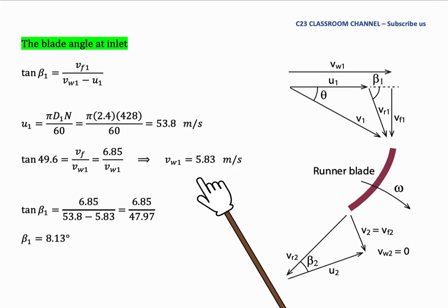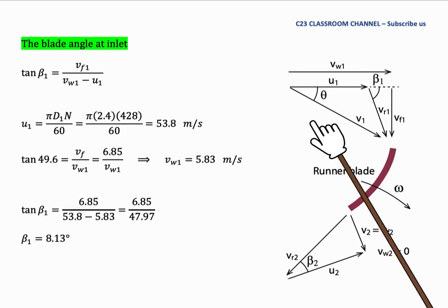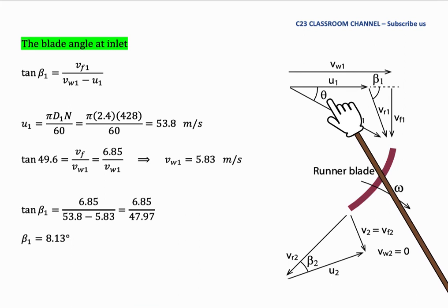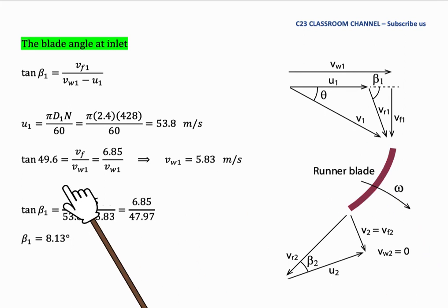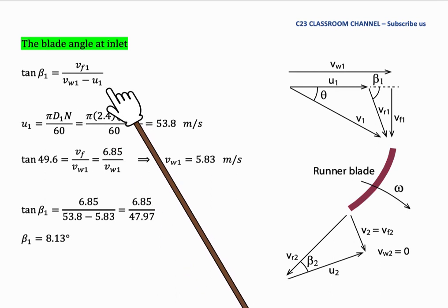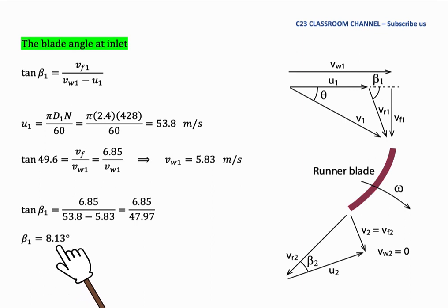Then we could calculate the velocity of VW1 here by using this equation. And we have advantage here because the tangent for θ is already calculated. It is equal to 49.6. We could use this equation to calculate VW1 here and it is equal to 5.83 meters per second. Then we substitute the value of VF1, VW1 and U1 in the equation. We could get β1 is 8.13 degrees.